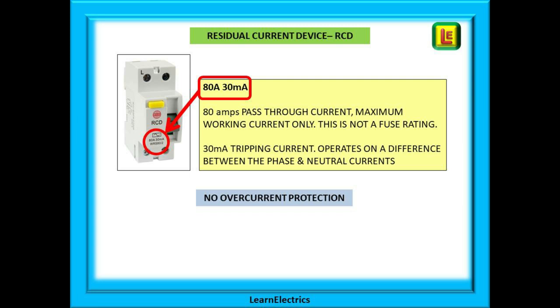The 30 milliamps shown on the front tells us the RCD will operate when the difference between phase and neutral reaches 30 milliamps. Larger tripping currents are available — for example 100 milliamps and 300 milliamps — but these are usually for fire protection, not for preservation of life.